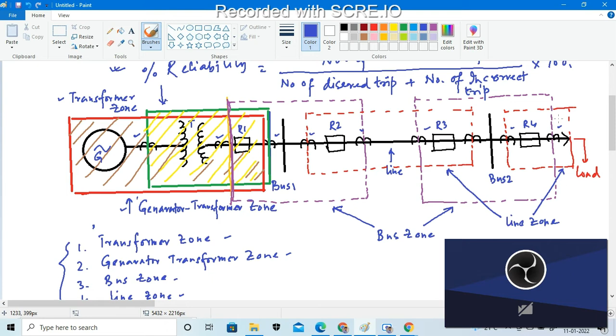Okay, so you will see that the transformer zone and the generator protection zone are overlapping with each other. The transformer zone and the bus zone overlap with each other, and the bus zone and line zone overlap with each other. So due to this particular overlap, there must be accountability of the fault in the circuit breaker that will arise. So we have to overcome that. How could I overcome? We have to connect the different CTs in particular lines, so that we will overcome to some extent the overlapping situations in the protection schemes.